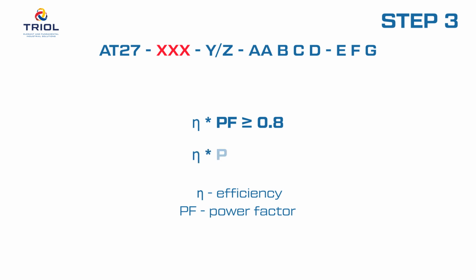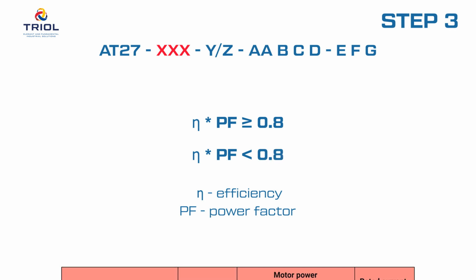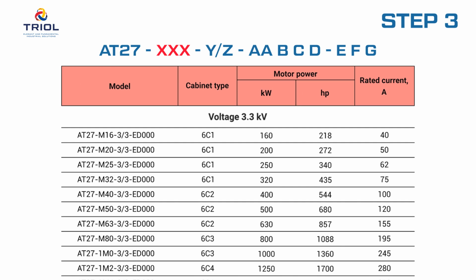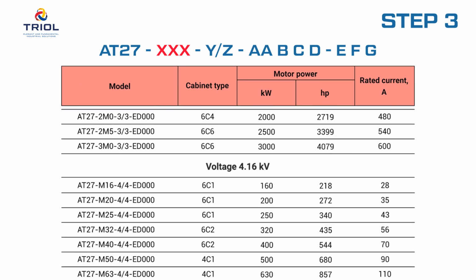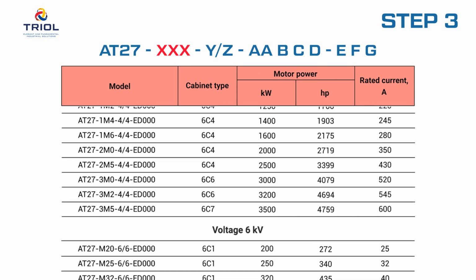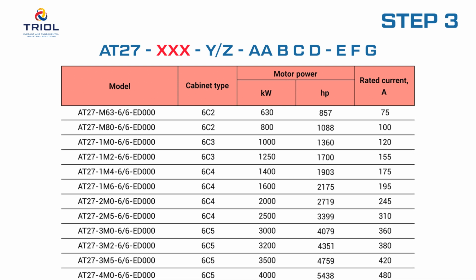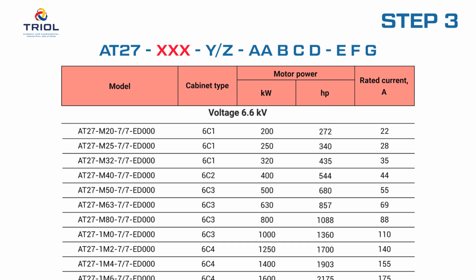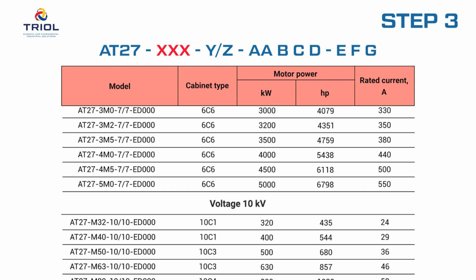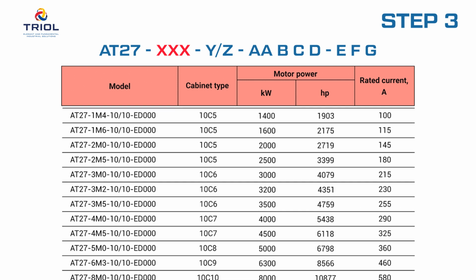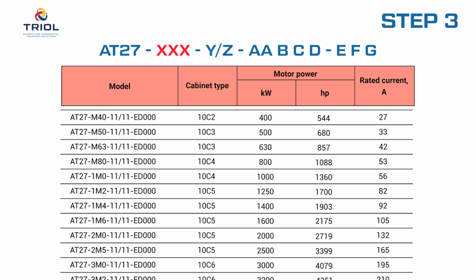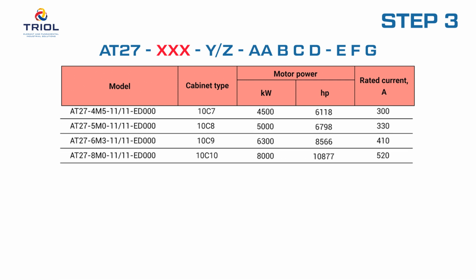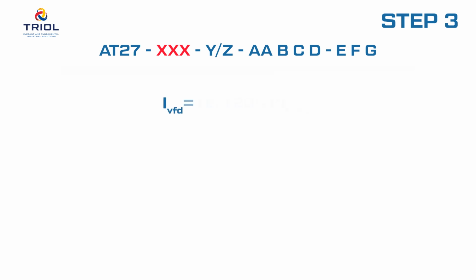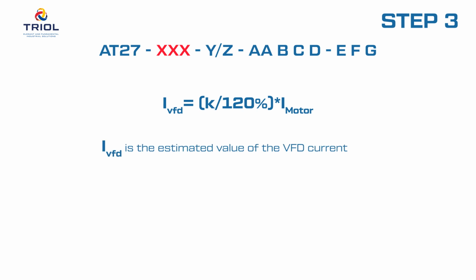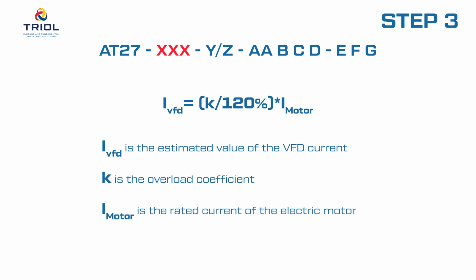If the product of efficiency and power factor of the electric motor is less than 0.8, the selection of the power inverter is carried out in the catalog, considering the rated output voltage and current of the AT27 VFD. Select the variable frequency drive from the catalog where the rated output current at the required output voltage is the higher closest value compared to the rated current of the connected motor. If we are talking about heavy starts with an overload coefficient of more than 120%, the choice of the inverter power is carried out according to the recalculated value of the output current of the electric motor, according to the following formula, where I-VFD is the estimated value of the VFD current, K is the overload coefficient, and I-rated EM is the rated current of the electric motor.